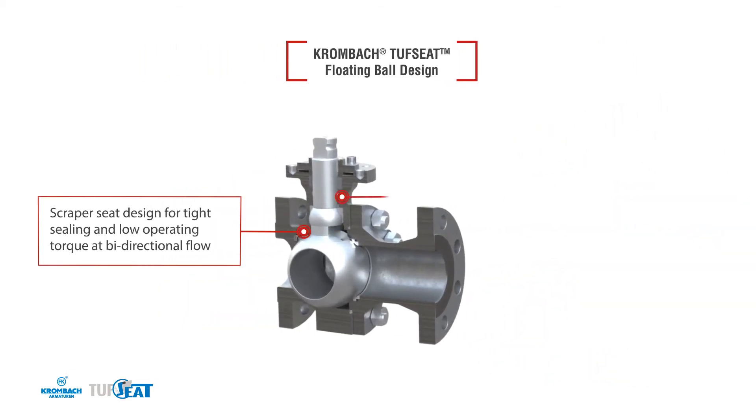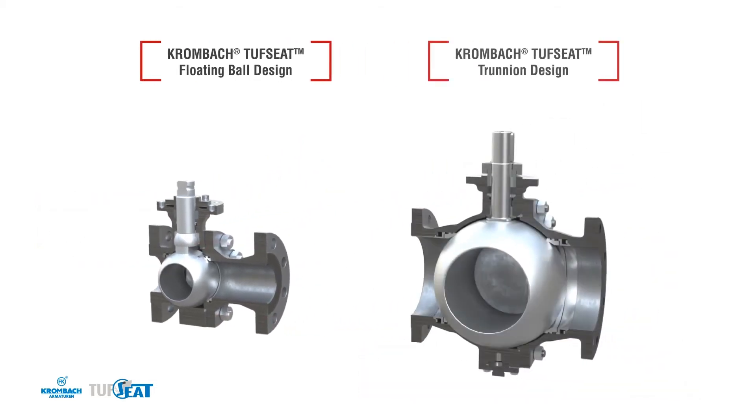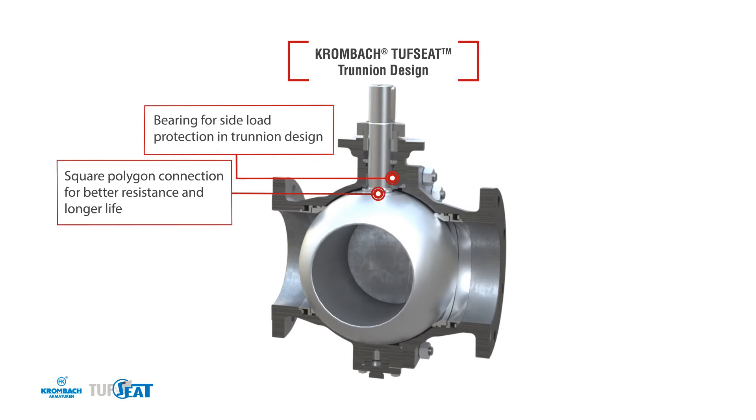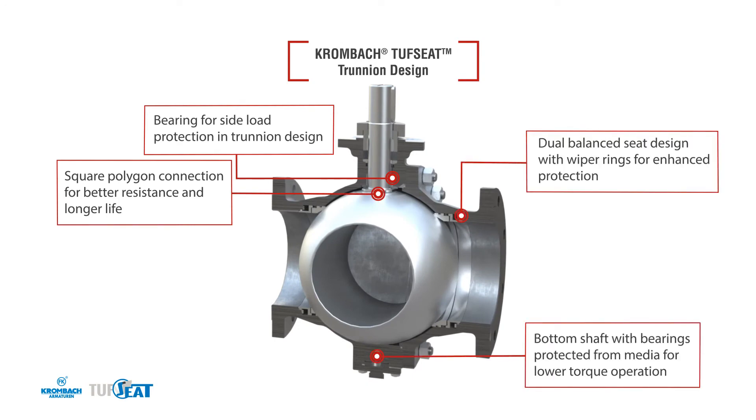All TUFSEAT Performance Valves are fitted with scraping seats for abrasive applications, best-in-class fugitive emissions packing arrangements, and 100% tested and certified fire safe as per API 607. The larger trunnion valves are also equipped with top and bottom bearing protectors, a square polygon connection between stem and ball for better torque transmission, and dual-balance seats with wiper rings to better protect the seats from the ingress of solids or contaminants.